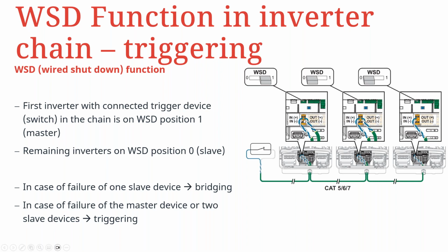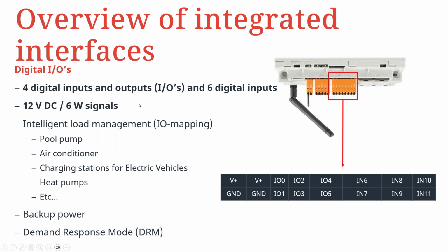So basically the out terminal of the first goes into the in terminal of the next, and that is the way it continues until the last inverter is connected. Usable cables are Cat 5, 6, and 7. Like I've mentioned earlier, the master, or the inverter connected to the trigger switch, should have the WSD switch in the 1 position. In the case of failure of one slave, it will be recognized as a bridging fault. But in the case of a failure of the master device or 2 slaves, this would result in the triggering of the switch.